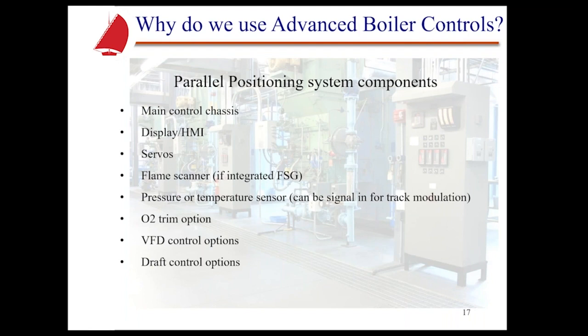This is where you're going to have to go back to normally the burner manufacturer for a recommendation. Now, as many people have gained experience over time, they know approximately what size they need for those applications. It's always better to have a larger servo than a smaller servo because of over torque requirements sometimes. Also, parallel positioning systems that have the integrated flame safeguard are going to require that you select a flame scanner, okay? So you'll need to do that based off of the type of fuels you're going to be burning.